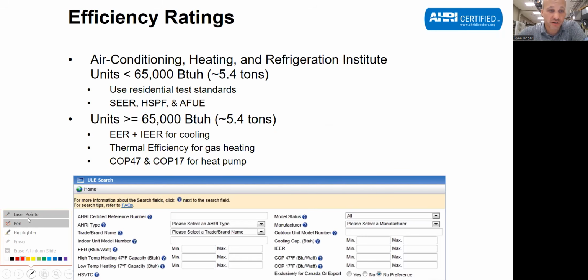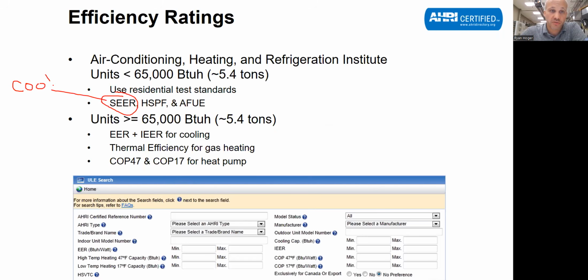You probably heard the term SEER. SEER only applies to 5 tons and less. Above 5 tons, there's no such thing as SEER. It doesn't exist. Never heard of it, right? SEER is my cooling efficiency. It stands for Seasonal Energy Efficiency Ratio, and it's for cooling. It has nothing to do with heating in any way.